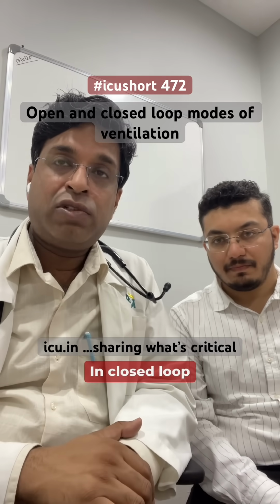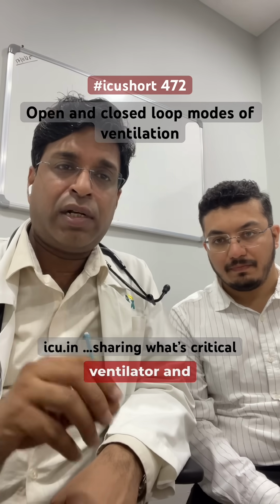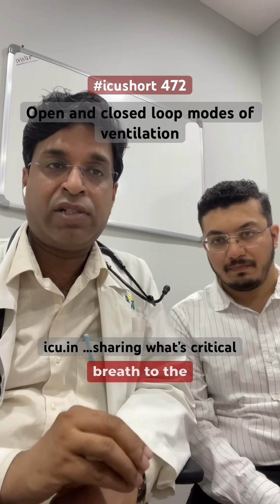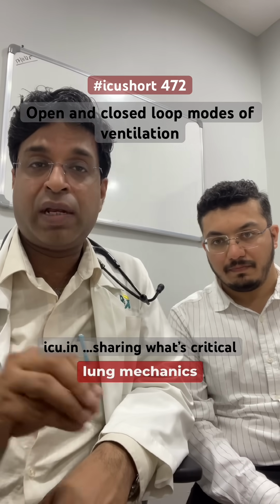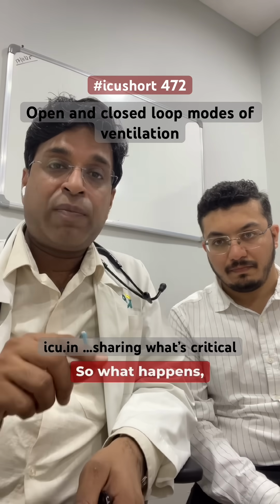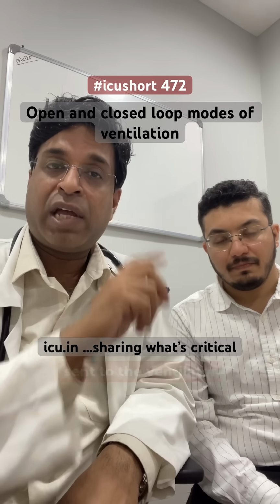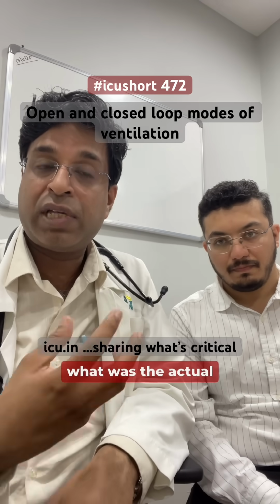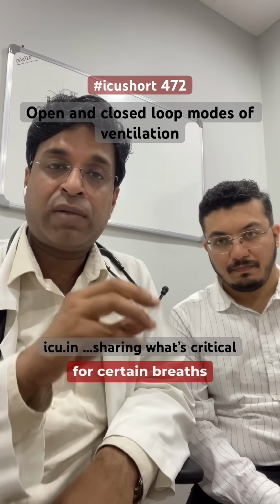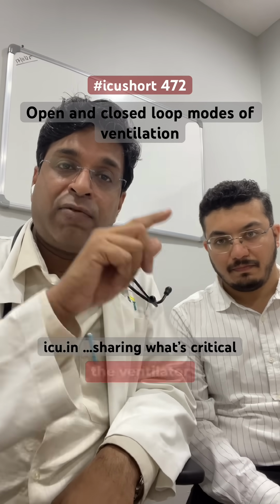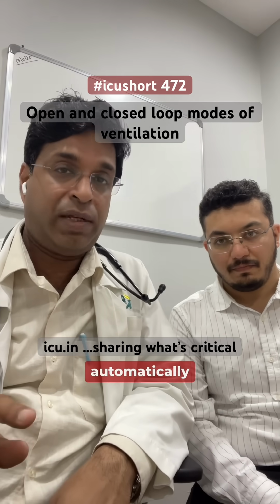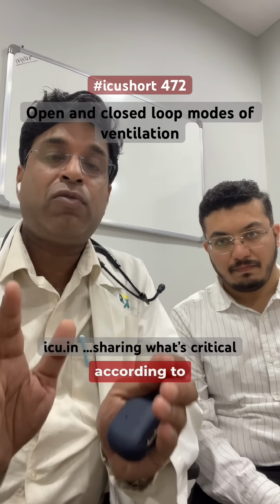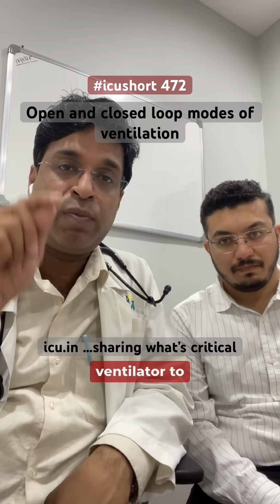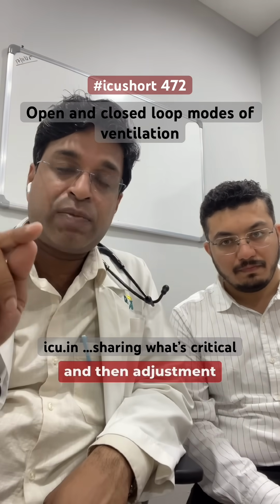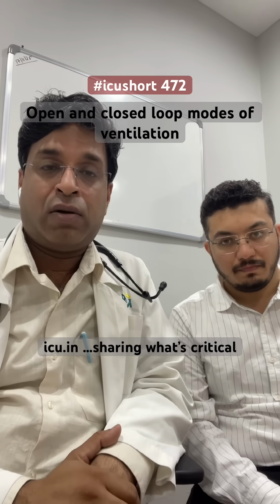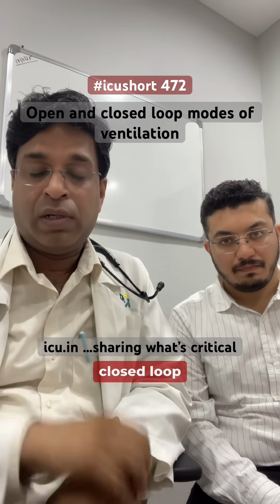What is closed loop? In closed loop, we decide certain settings on the ventilator, and based on these settings the ventilator delivers the breath to the patient, and based on the lung mechanics of the patient, there may be certain variations. These variations are then sent back to the ventilator by a feedback mechanism. So the ventilator registers what was the actual breath delivered, keeps observing for certain breaths, and then based on that feedback, the ventilator tries to adjust certain settings automatically so that the actual breath is delivered according to what we have set. So it's a closed loop system: ventilator to patient and patient to ventilator feedback, and adjustment of the ventilator setting within that range. So these are the open loop and closed loop ventilator modes.